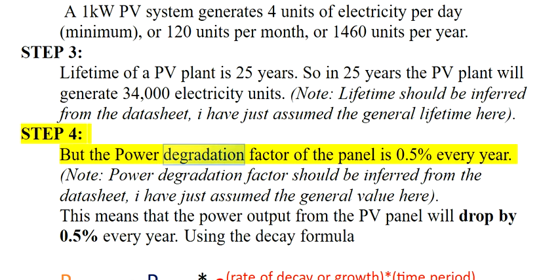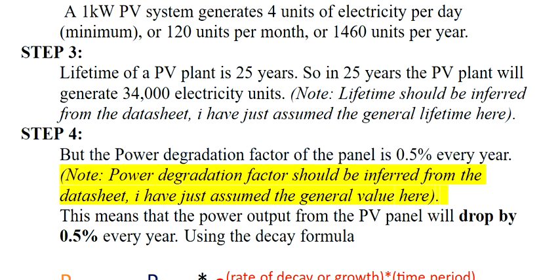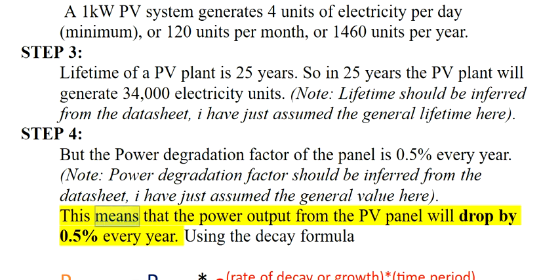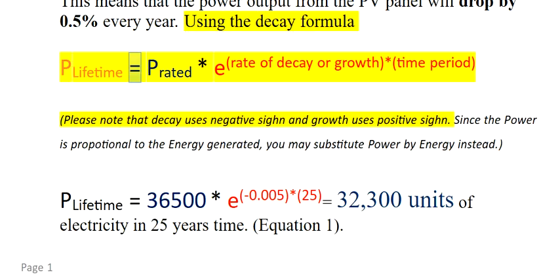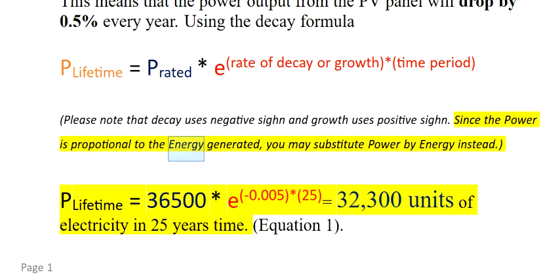Step 4: The power degradation factor of the panel is 0.5% every year. This means that the power output from the PV panel will drop by 0.5% every year. Using the decay formula: P-lifetime equals P-rated asterisk E raised to the power of (rate of decay asterisk time period). Please note that decay uses a negative sign and growth uses a positive sign. Since the power is proportional to the energy generated, you may substitute power by energy instead.